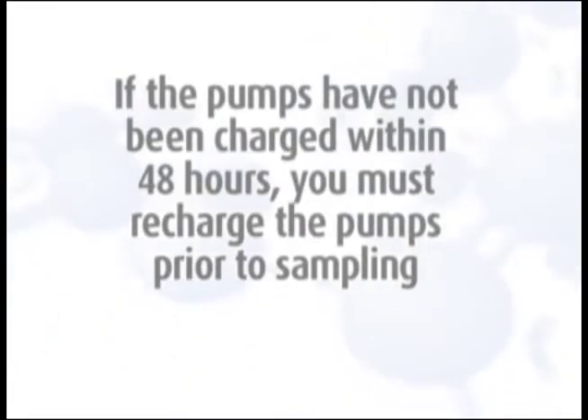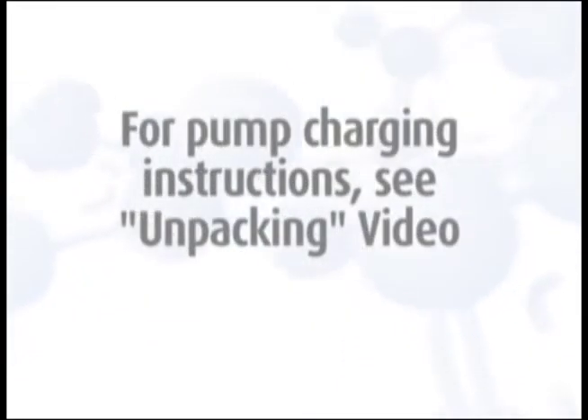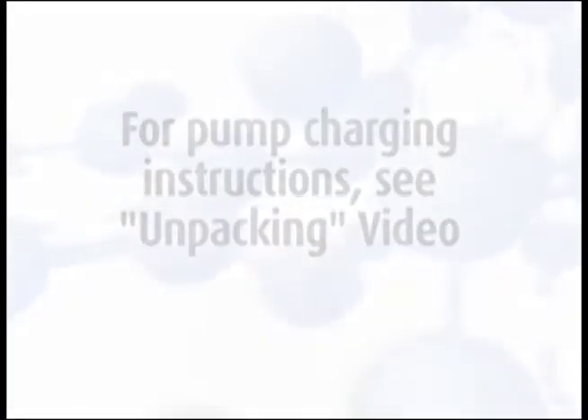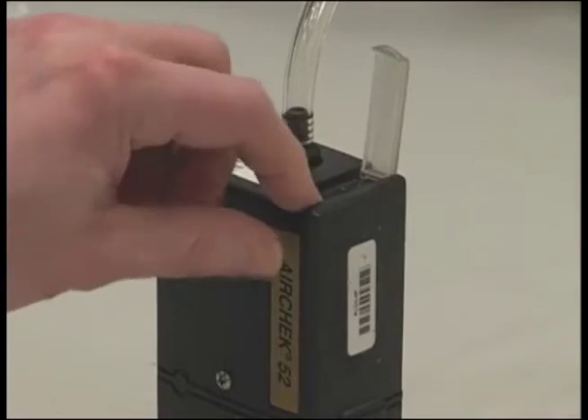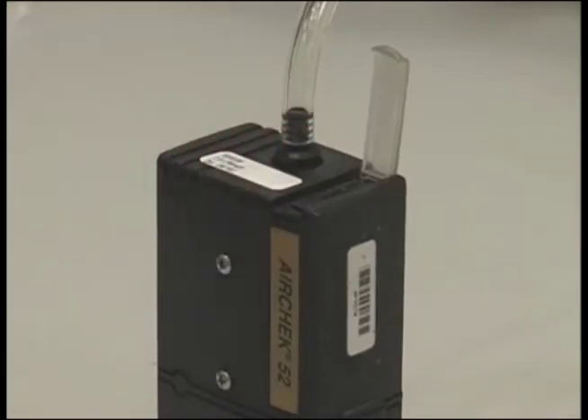To calibrate the pumps, they must be charged. If the pumps have not been charged within the past 48 hours, you must recharge the pumps prior to sampling. Start the pumps so they can be warming up. They need to run at least 3 minutes before you begin the calibration.